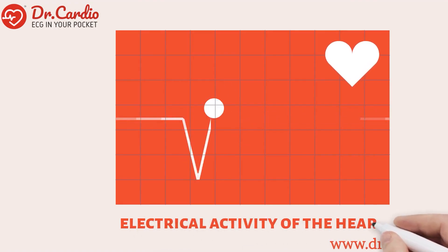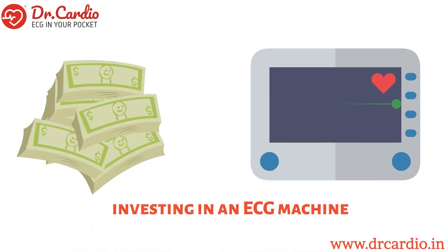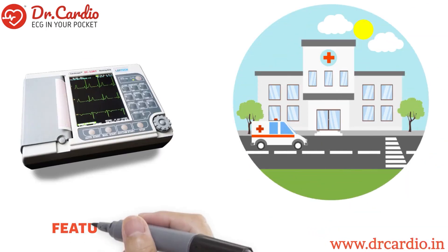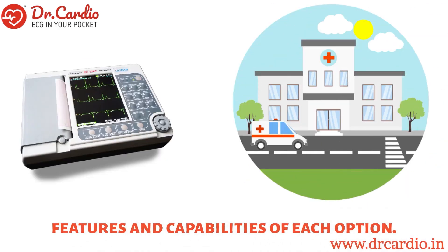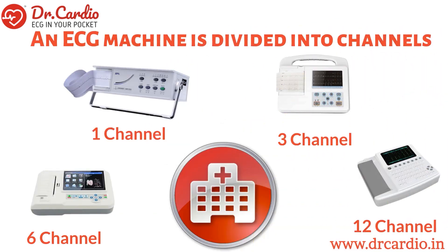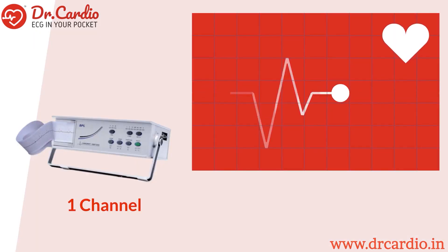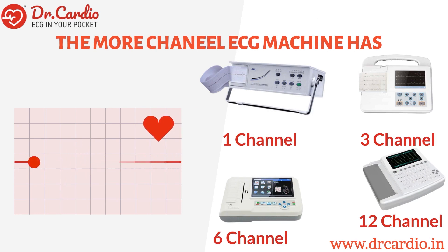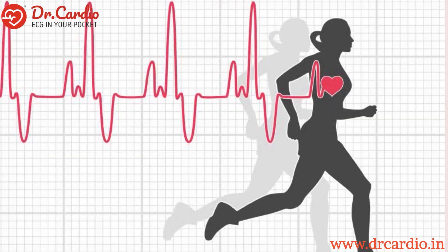ECG machines are essential tools used to record the electrical activity of the heart. When investing in an ECG machine, it is important to understand the features and capabilities of each option. An ECG machine is divided into channels, and a channel is a single lead that records the electrical activity of the heart. The more channels an ECG machine has, the more detailed the electrical activity of the heart can be analyzed.